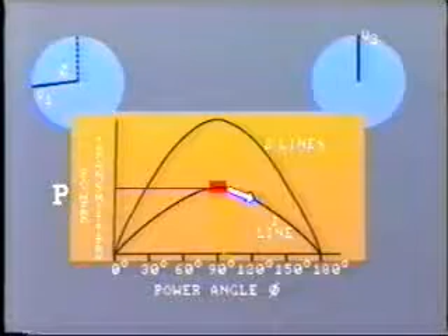Now, in this precarious situation, any disturbance on the power system, say a loss of load or a loss of power generation, may cause the voltage at V1 to advance further, or perhaps the voltage at V2 to lag, such that the load angle between them exceeds 90 degrees. Beyond this point, the load transfer across the line actually decreases, so the generators at bus 1 accelerate in an attempt to increase the load transfer. This in turn increases their angle of lead even farther, so that the power transfer continues to decrease. At this point, the generator rotors are advancing on those at bus 2.